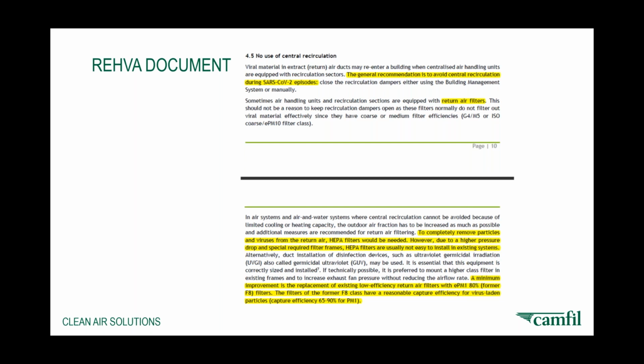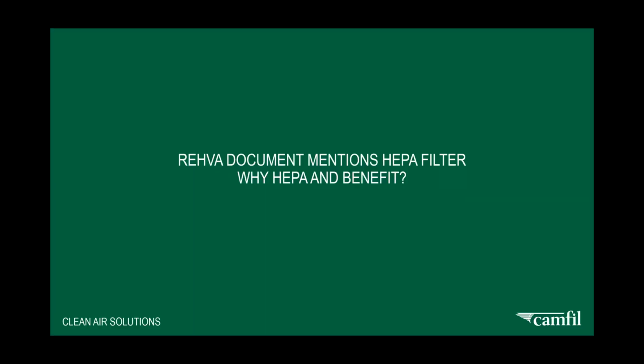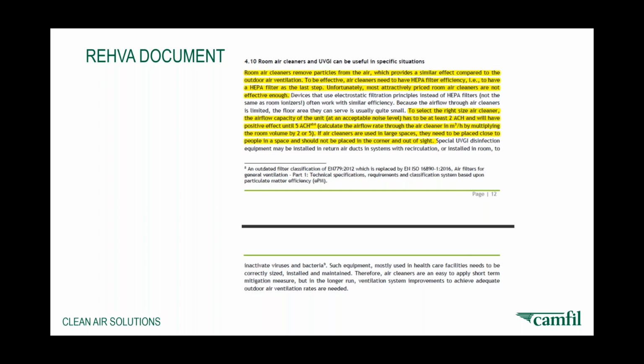But the REHVA document is now mentioning HEPAs. So why have they mentioned HEPAs, and what's the benefit? They mention HEPAs and they mention room air cleaners. They mention room air cleaners and they mention UVGI sterilization of air, etc. They mention both of these technologies specifically. So we're looking at filters and air cleaners today because of the recommendation on HEPAs. So to be effective, they're saying air cleaners need to have HEPA filter efficiency.